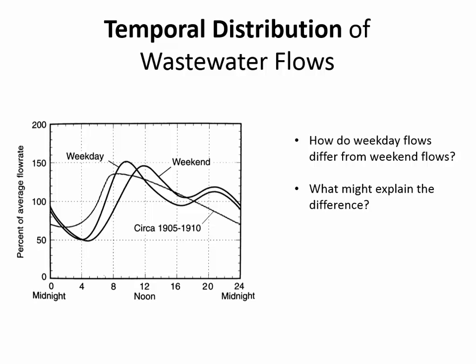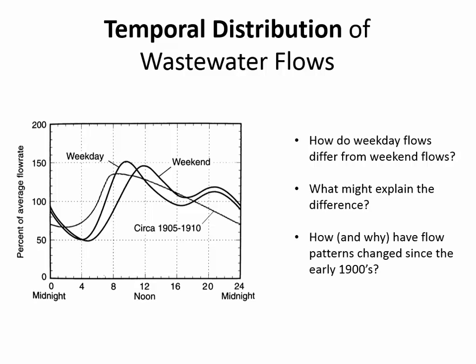It's really important for us to understand when the wastewater is coming to the treatment plant. We've got an ecosystem of bacteria living at the treatment plant on the waste that comes from the population upstream, and we have to keep them alive because they're breaking down the BOD. It's a really diverse ecosystem of microorganisms. We have to know these patterns backwards and forwards to design flow equalization storage and give them a steady supply of the food they're breaking down.